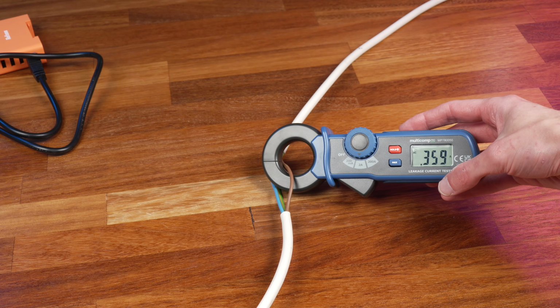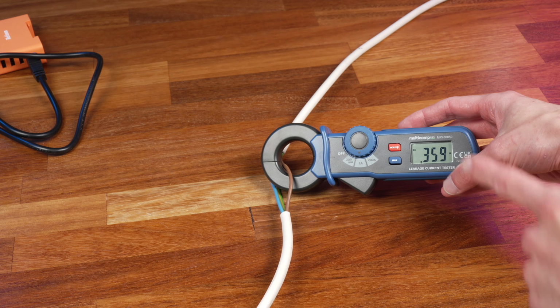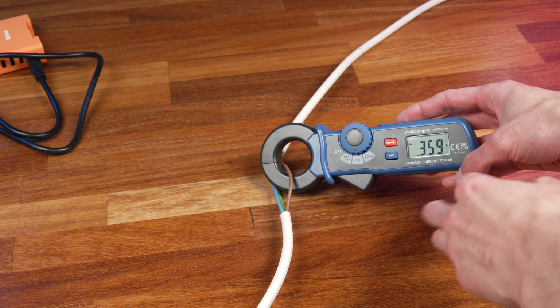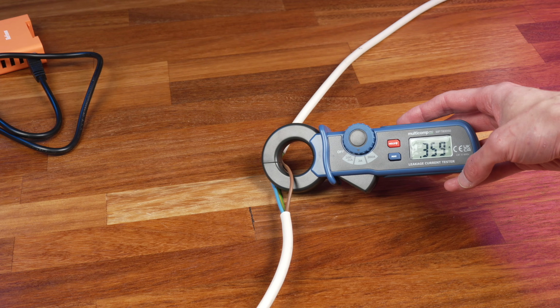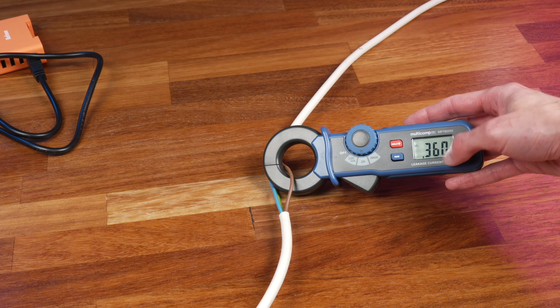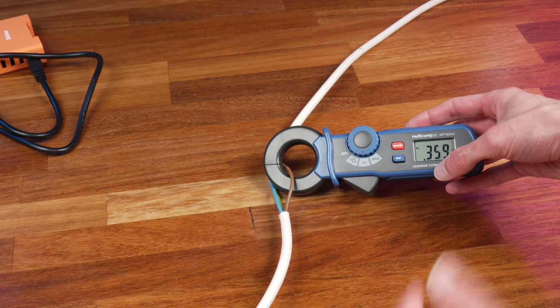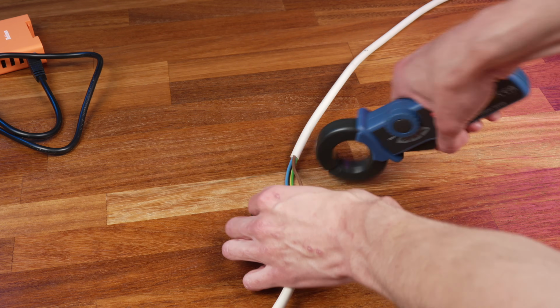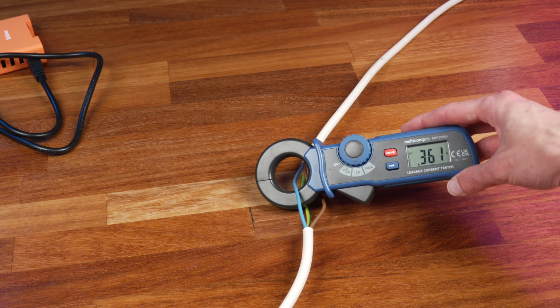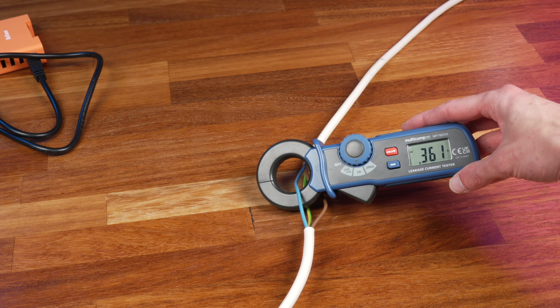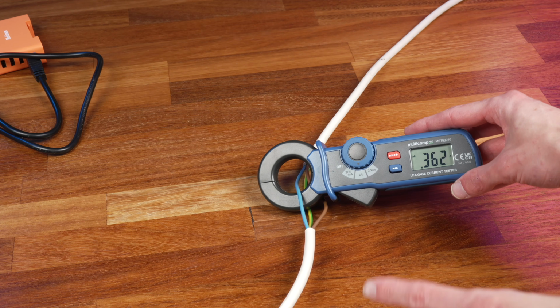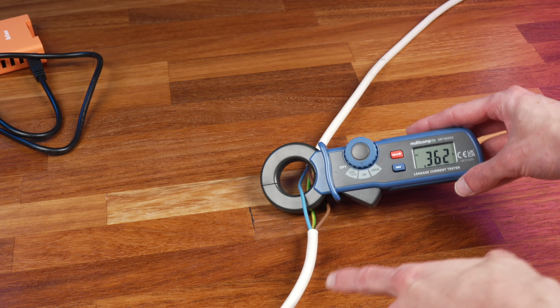However, you don't have to connect the CT around the line conductor. As you can see here, we're getting a reading on the line conductor of, what, 360 milliamps or so. But if we come off of that wire there, and instead go around just the neutral on its own, as you can see, we're measuring the same value. And that's because, excluding any earth leakage, the same amount of current will flow up the line and then back down the neutral.